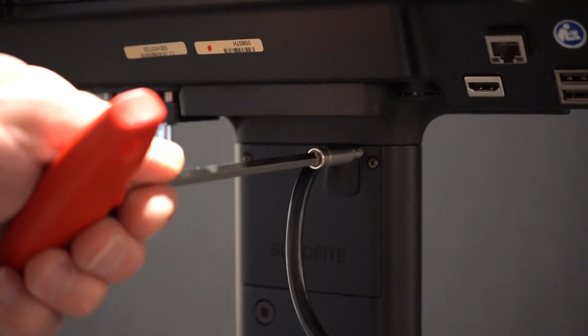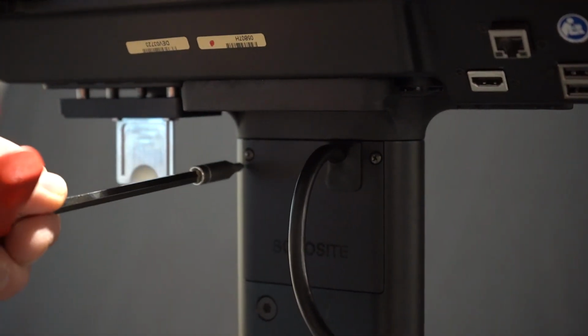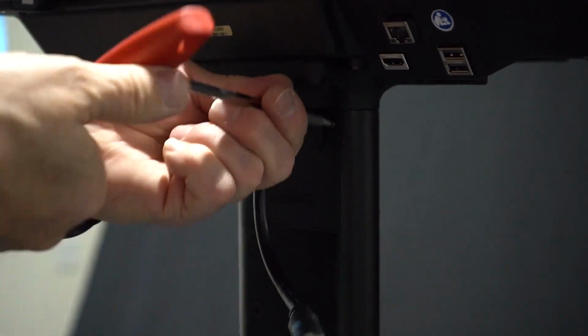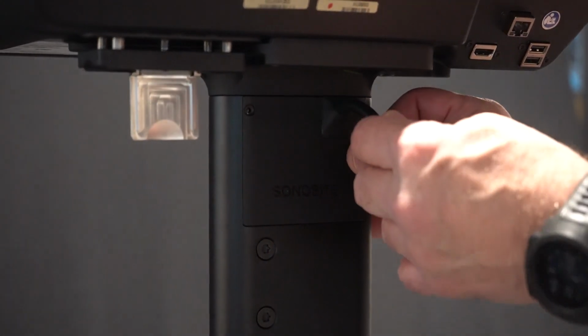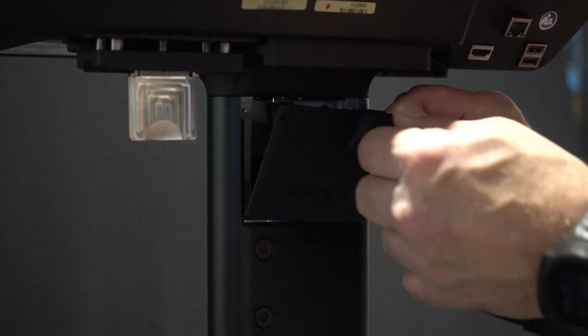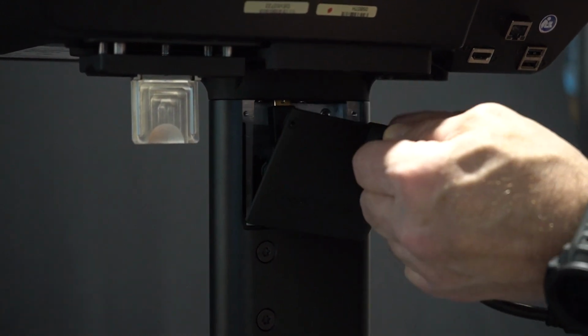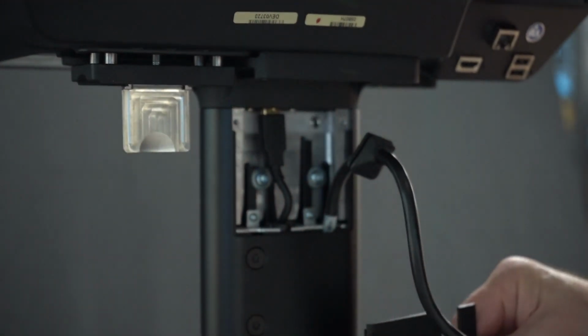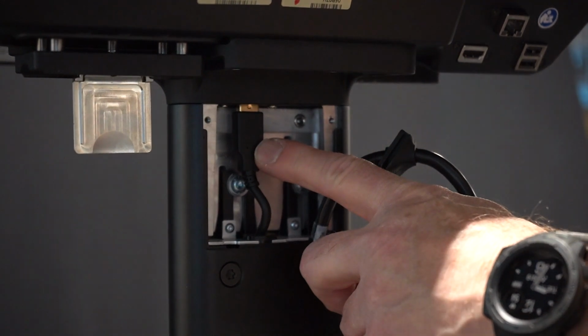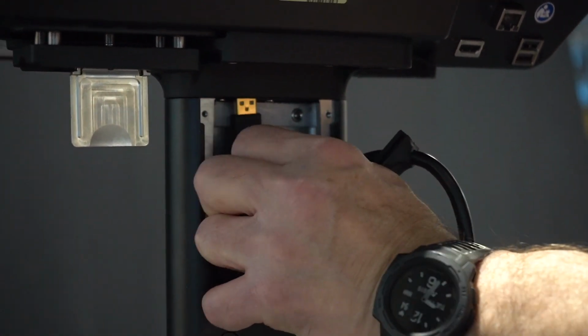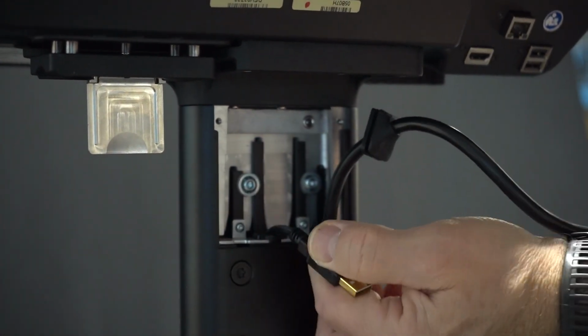Use the magnetic bit driver and the number 1 Phillips head bit to remove the 2 screws securing the stand column cover. Loosen the power cable grommet from the stand column cover and remove the stand column cover from the stand. Disconnect the USB cable in the inner column of the stand from the USB port on the stand head.